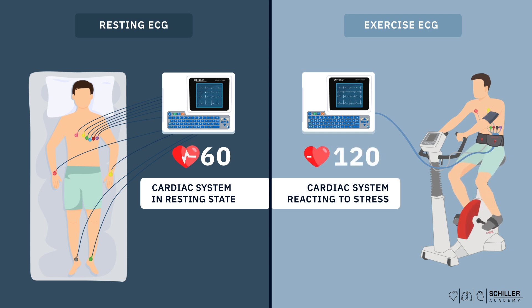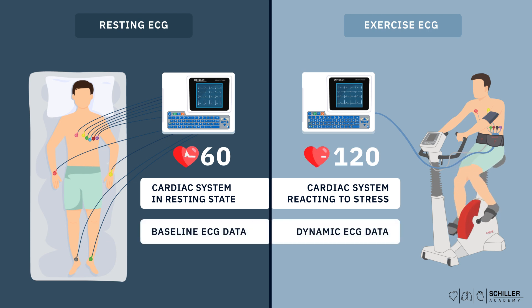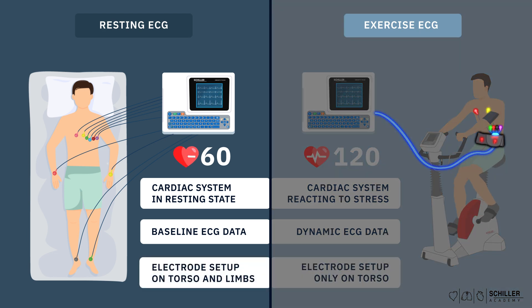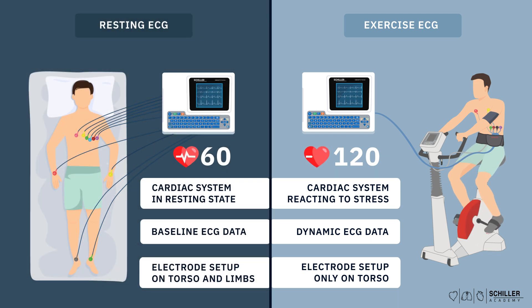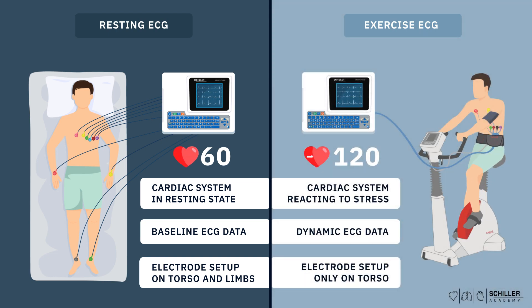The most obvious difference between a resting ECG and an exercise ECG is that once the patient is at rest, and once the patient is exposed to physical stress, which is meant to increase oxygen demand. Hence, the exercise ECG can reveal heart conditions that might not be evident in a resting state, and can provide more dynamic information. The electrode setup of an exercise ECG differs slightly from a resting ECG, as the limb electrodes are transposed to the torso of the patient to reduce movement artifacts induced by running or pedaling.